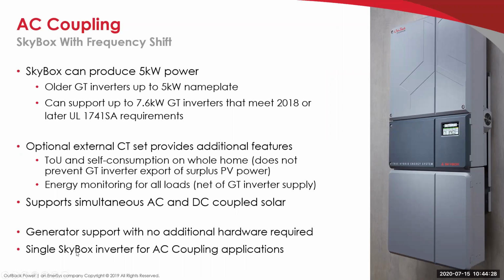One limitation, though, is that there's only a single Skybox inverter for AC coupling applications, so you cannot stack the Skyboxes. So one inverter is the maximum you can do with Skybox. And with the Radian, we will support up to 3. I know people have done 4 or even more, I believe, Radians in parallel, just make sure that they're all set to be on all the time. So don't use the power saving mode when you do that.